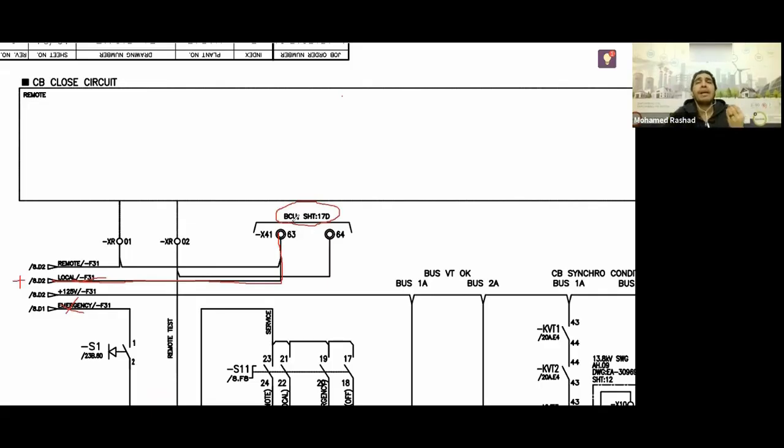Very good. And then this BCU, which is the Bay Control Unit, acts as the control room that used to exist in old station units. You can monitor from it, get readings from it, see what is closed and what is open, and you can also control from it. In the past, this control room was connected to the SCADA system. So the control room would output protocol 101 or 102 and go to something like the RTU or others. Then we would go to the gateway, and from the gateway to the SCADA.